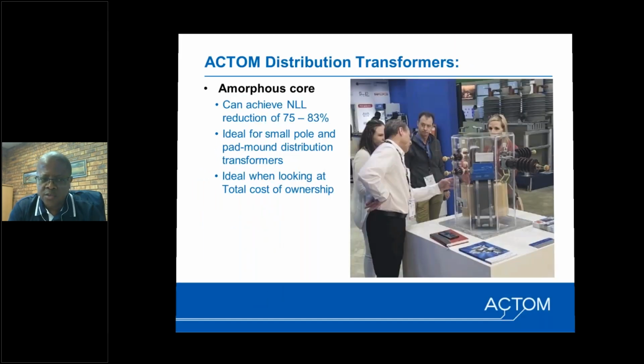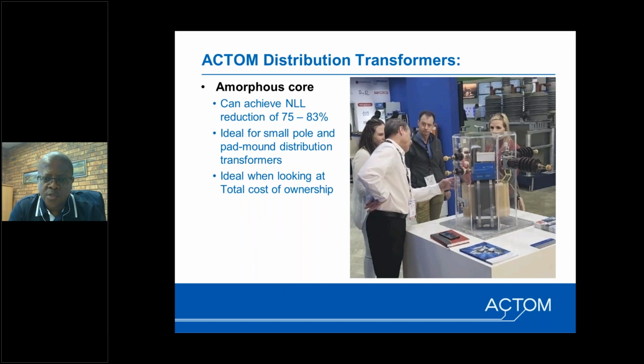Amorphous core transformers that I touched on a bit earlier, those are meant to reduce the no-load loss. And the material supplier of the core material guarantees a reduction of 75%. But we were able to achieve 83% reduction in no-load loss on the transformers that we manufactured. So these are ideal for pole and pad mount transformers, and if you're looking at total cost of ownership because of the reduction in losses.